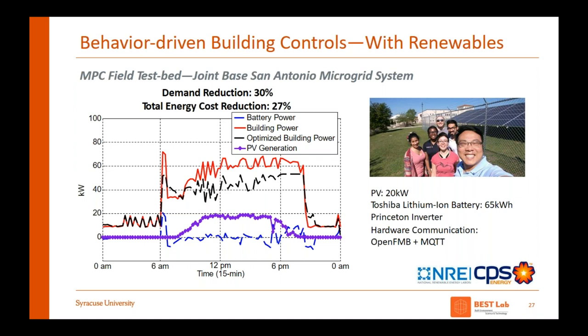We invented communication algorithms to talk to the inverter and the battery system, controlling when the battery charges and discharges. This is the battery power, charge and discharge. The red line is the actual building power, and this is the optimized building power based on our algorithm, and this is the PV generation. The result is that we can reduce peak demand by 30%, and total energy cost by about 27%, using the PV and battery system.